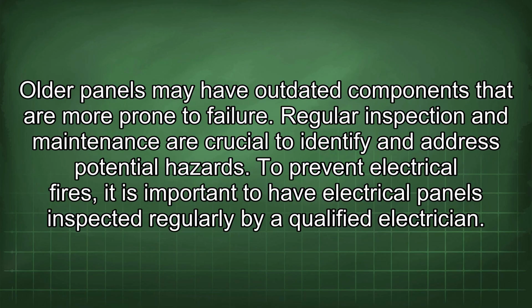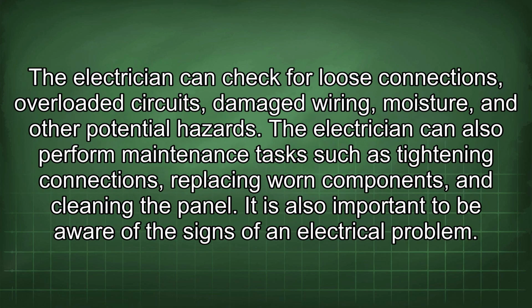Older panels may have outdated components that are more prone to failure. Regular inspection and maintenance are crucial to identify and address potential hazards. To prevent electrical fires, it is important to have electrical panels inspected regularly by a qualified electrician. The electrician can check for loose connections, overloaded circuits, damaged wiring, moisture, and other potential hazards. The electrician can also perform maintenance tasks such as tightening connections, replacing worn components, and cleaning the panel.